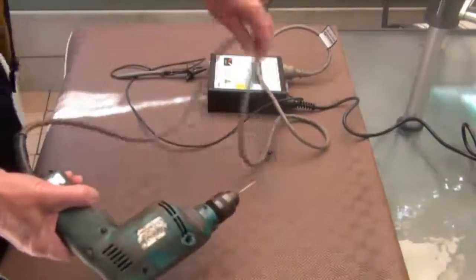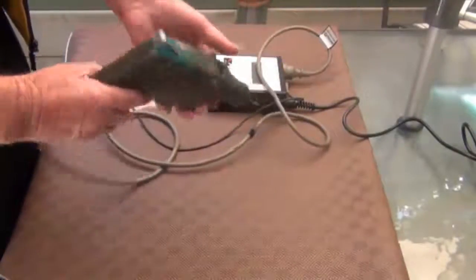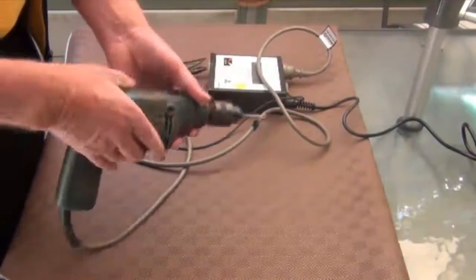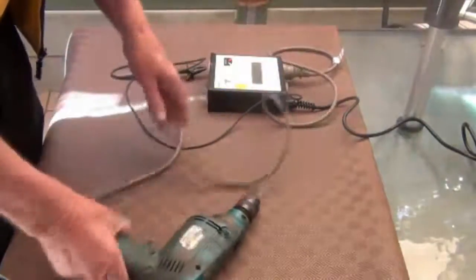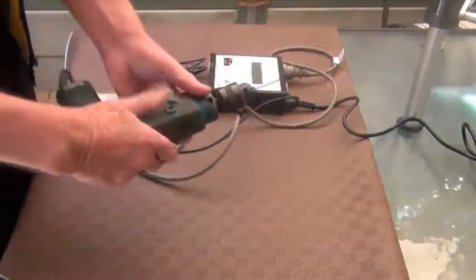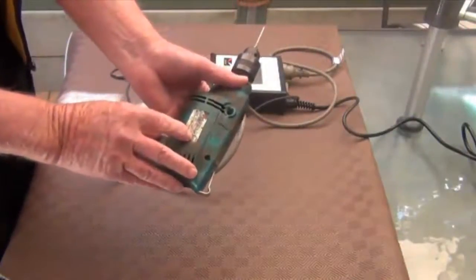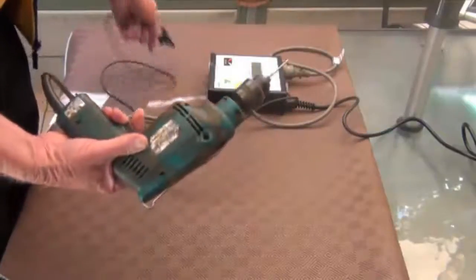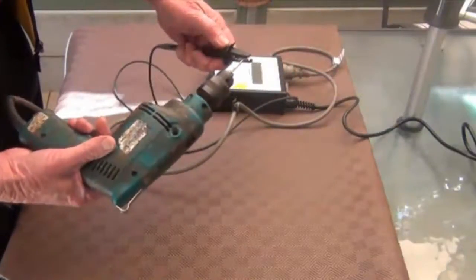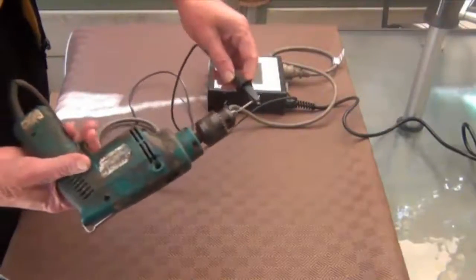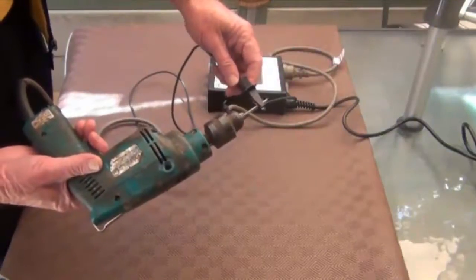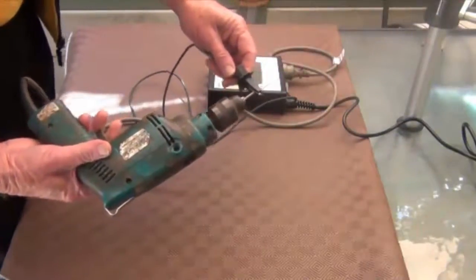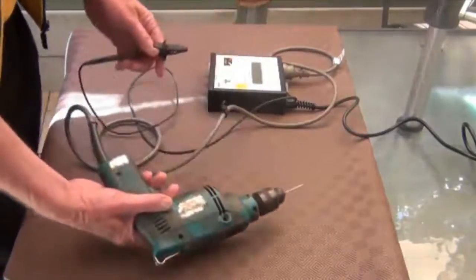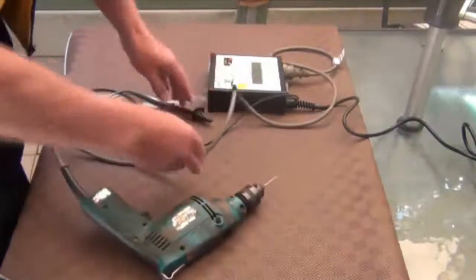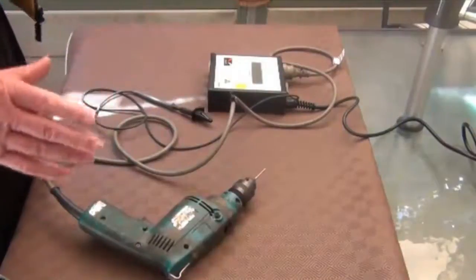You will recall when you're testing Class 2 equipment, you do your normal physical check, check your lead is okay, no problems, check the case isn't damaged, check the Class 2 symbol, connect your probe to the smooth shank of a drill, run it, read the result, and that's the end of the test. There is another test you can do.